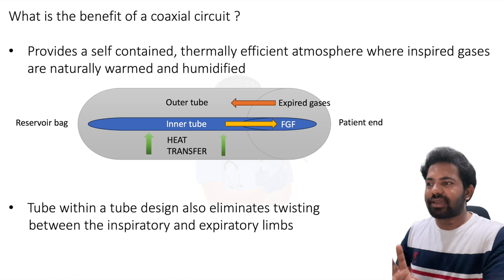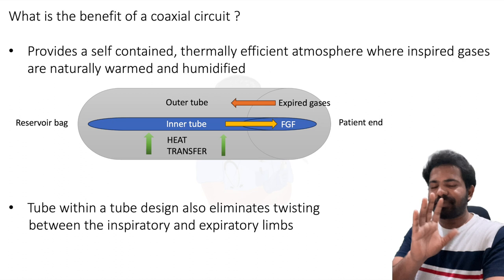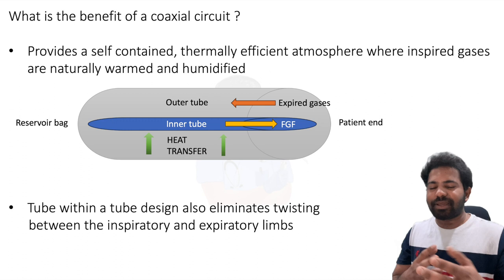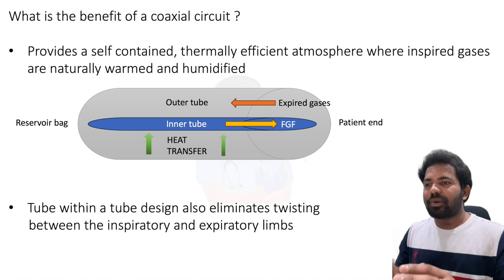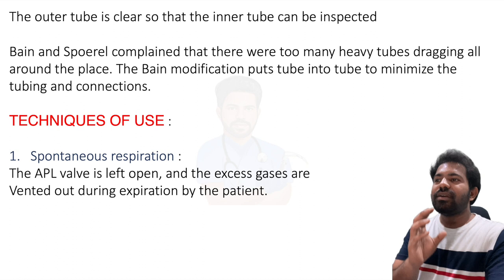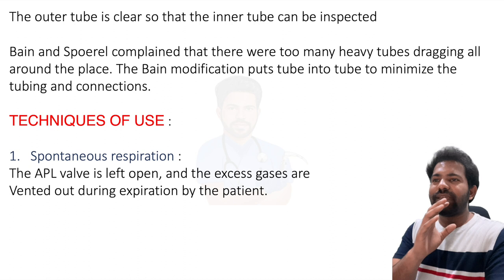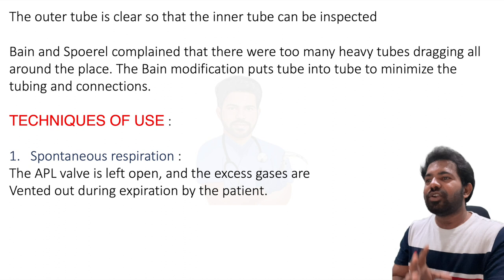The tube-within-a-tube design also eliminates twisting between the inspiratory and expiratory limb — just as a BP cable and ECG cable can become intertwined, two separate limbs risk disconnection, kinking, and twisting. These problems are eliminated by the coaxial model. The outer tube is clear and transparent so the inner tube can be inspected for any damage, holes, or leaks. Bain and Spoerel felt too many heavy tubes were dragging around, so the modification minimizes tubing and connections.